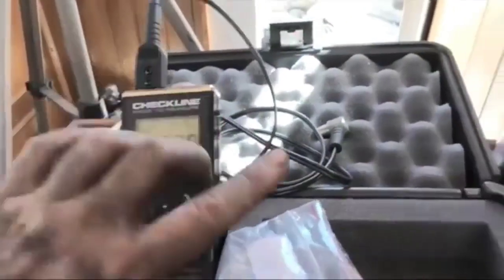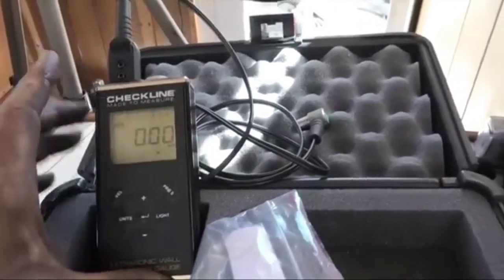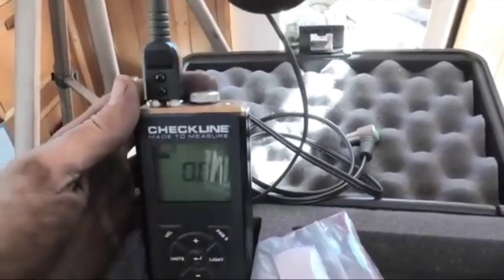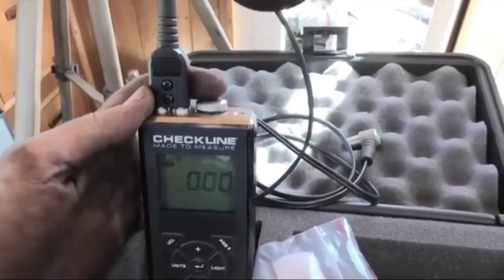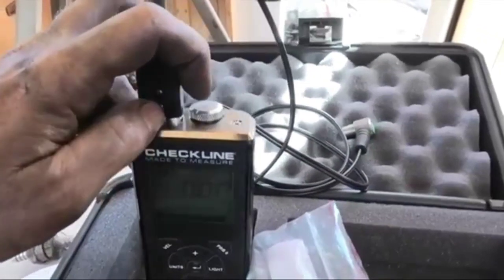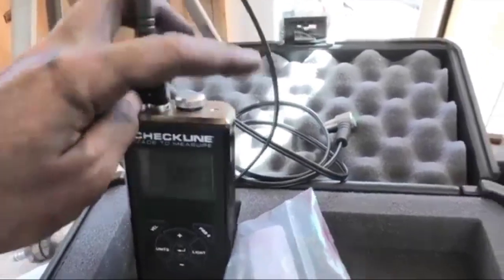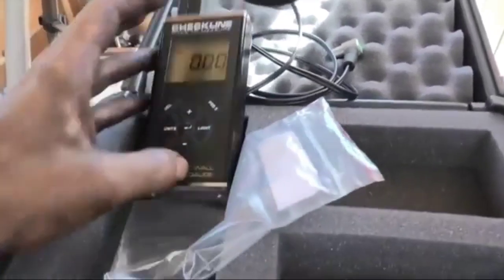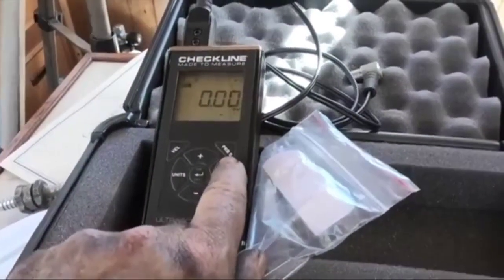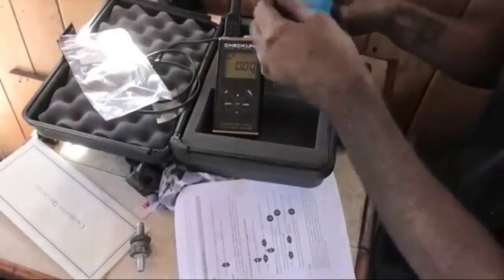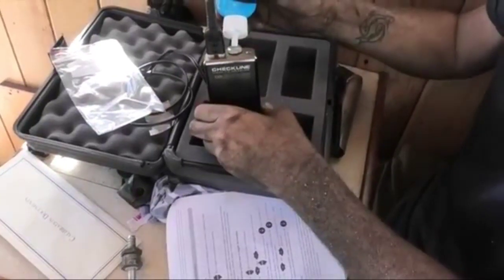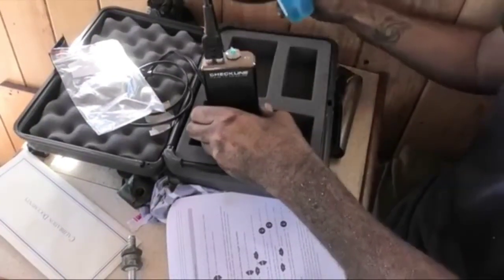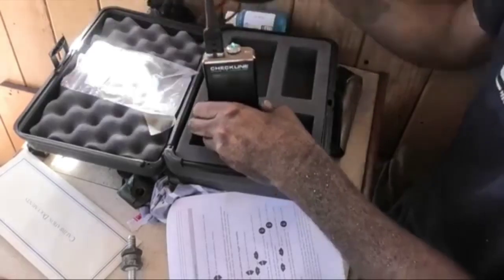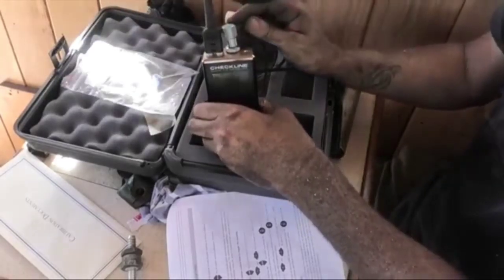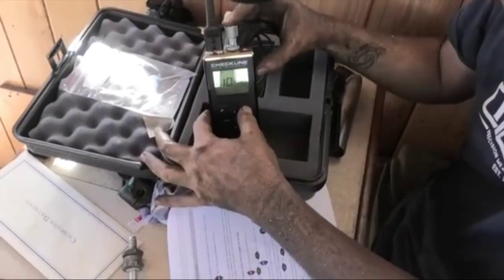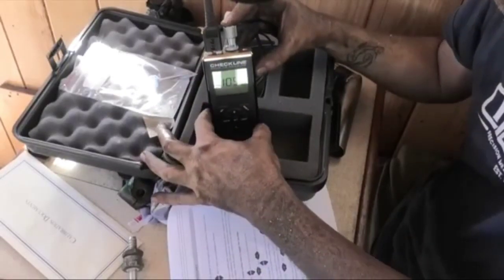To zero the unit, we put the transducer against a piece of metal of a known thickness, and what's a really cool thing about this design is the piece of metal you use for the calibration is the battery cap here. So all we need to do is put a drop of the coupling solution onto the cap, put the transducer on there, and hit here the PRB0 button. So, get our solution, put a little dob on the top, get our transducer, then once we're holding it down, press that button, and we're done.